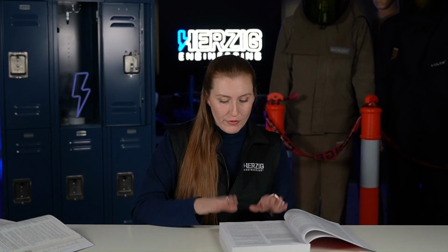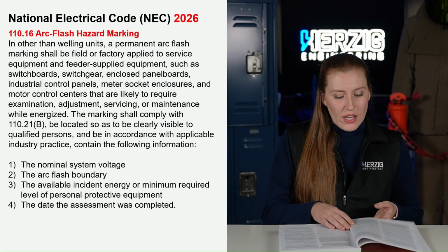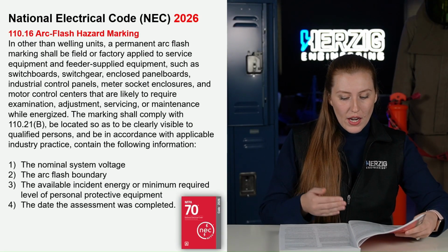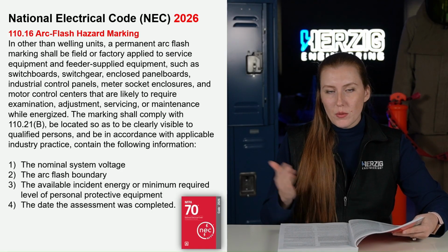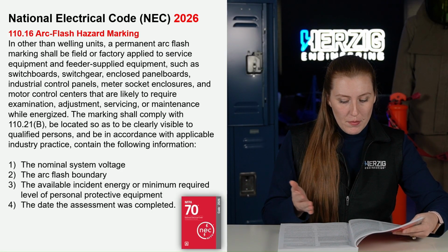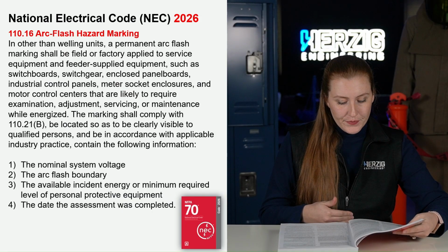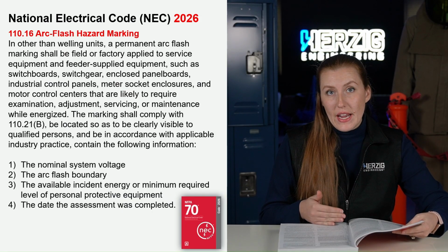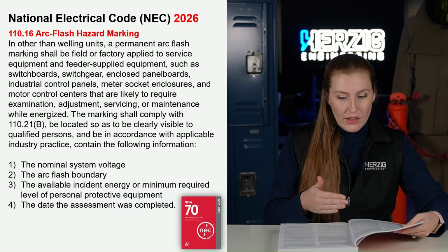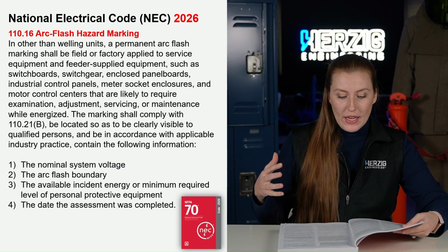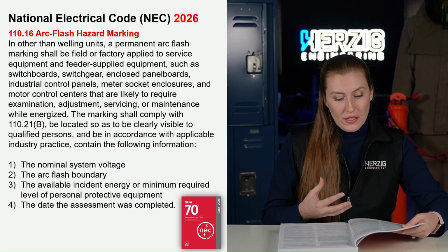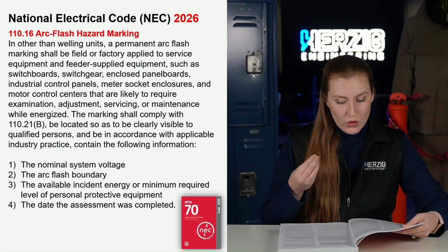Now let's go look at the 2026 edition, because the 2023 is out. We're going to focus on the 2026 edition now. In Article 110.16, the title had a slight change: arc flash hazard marking. And a lot of that verbiage is very similar to what we just read, but it also goes on to say that it'll need to contain the following information. And they give 4 points here, making it more prominent for you to recognize.